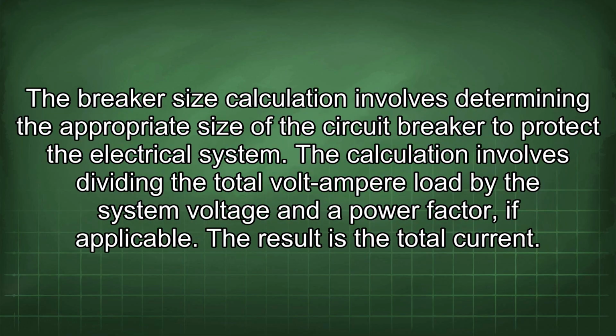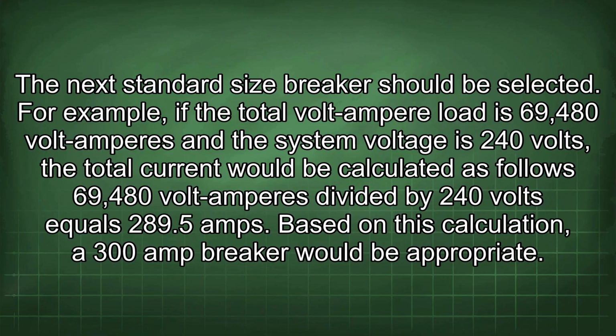The breaker size calculation involves determining the appropriate size of the circuit breaker to protect the electrical system. The calculation involves dividing the total volt-ampere load by the system voltage and a power factor, if applicable. The result is the total current. The next standard size breaker should be selected. For example, if the total volt-ampere load is 69,480 volt amperes and the system voltage is 240 volts, the total current would be calculated as follows: 69,480 volt amperes divided by 240 volts equals 289.5 amps. Based on this calculation, a 300 amp breaker would be appropriate.